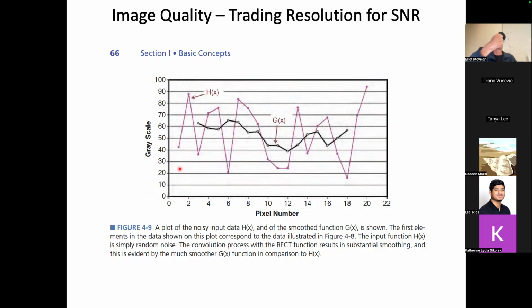When you take the antenna and bring it closer to the patient, even if they're not in the magnet, the noise goes up. The noise is from the patient, from the molecules jiggling around inside the patient. And the patient's at a higher temperature, right?